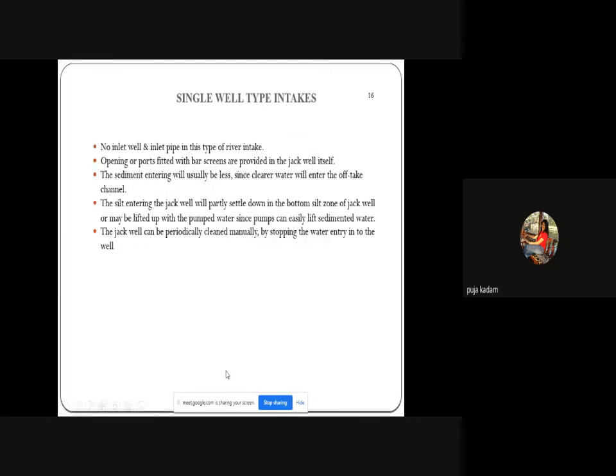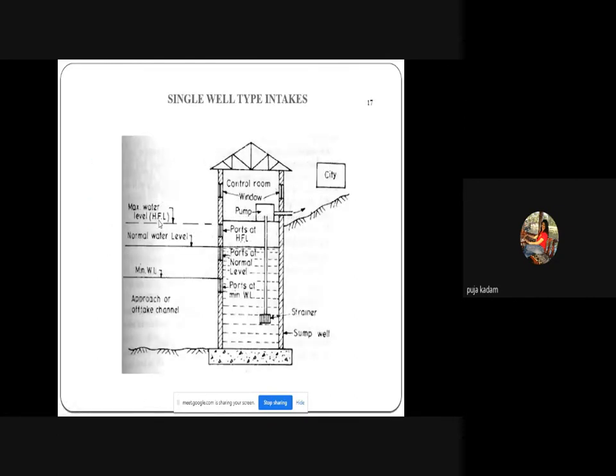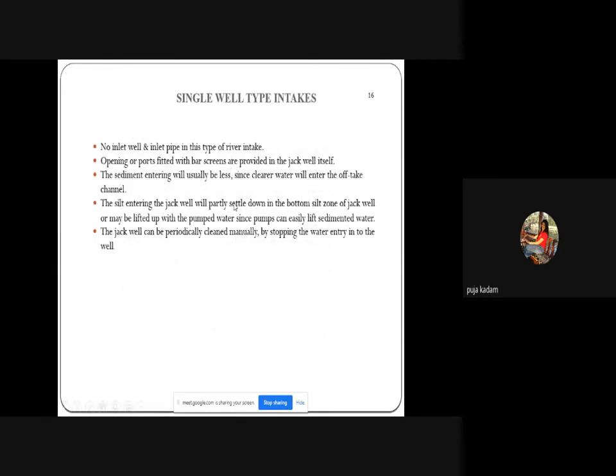The sediment entering will usually be less in the single-well type since clear water enters from an off-take channel — a diverted channel away from the main river where sediments mostly deposit on river sides. Any sediment entering the jack well will settle at the bottom silt zone, or may be lifted with pumped water since pumps can easily lift sedimented water. The jack well can be periodically cleaned manually or by stopping water entry.